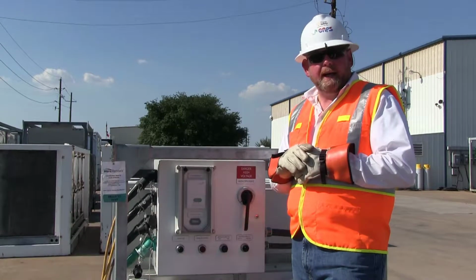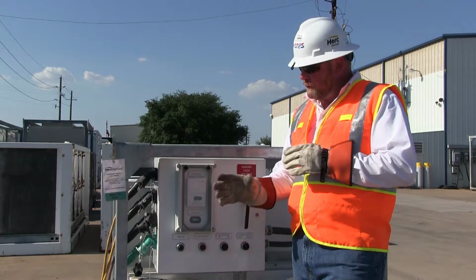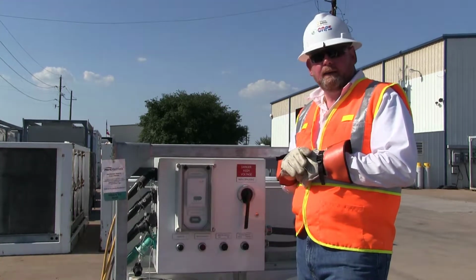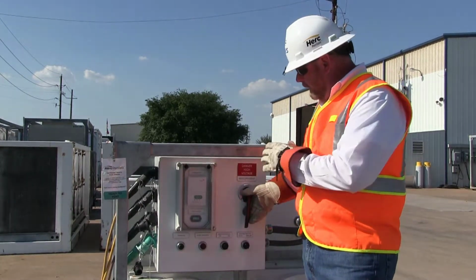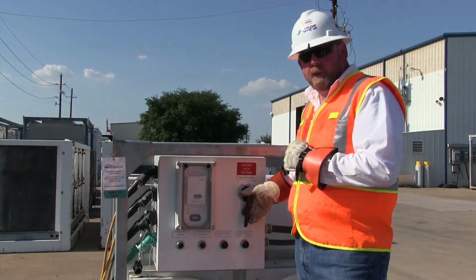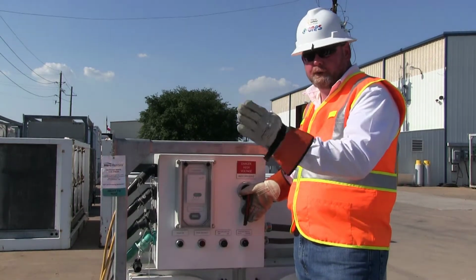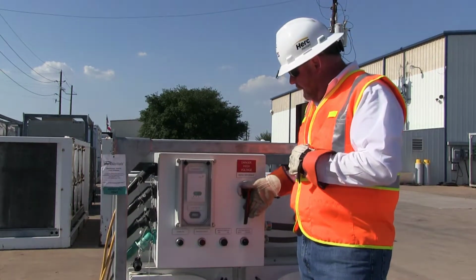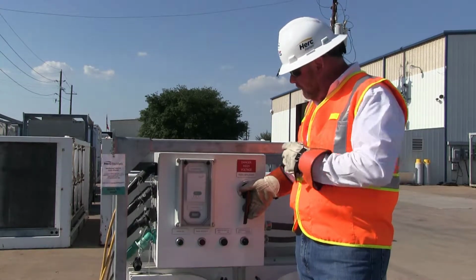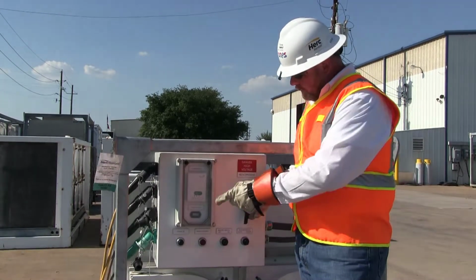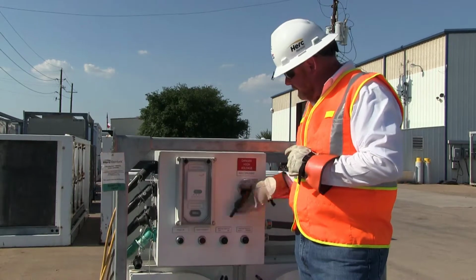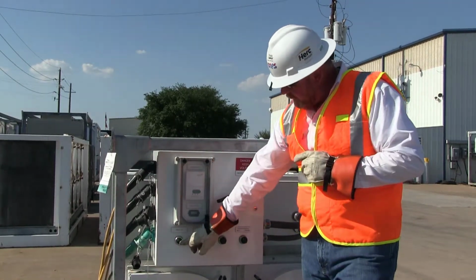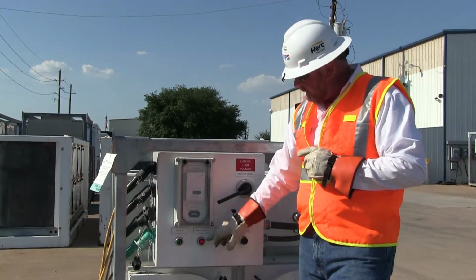We've removed our lockout and tag out from our primary power source, so our cam lock cables are hot now. All of our equipment features an integrated breaker, main disconnect port. You'll just need to protect your cable off your generator or main power source. So I'm going to turn on the main power here, 460 volt 3-phase. We're going to look for power, and we're going to check our phase. As I turn it on, you can see our power light's on, but our phase incorrect light is on.